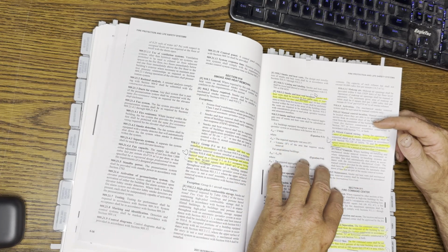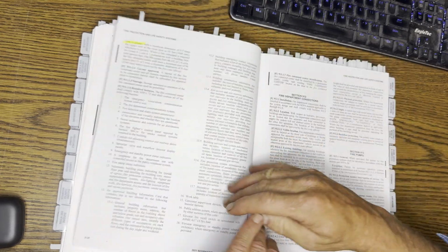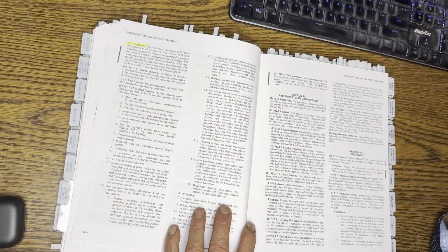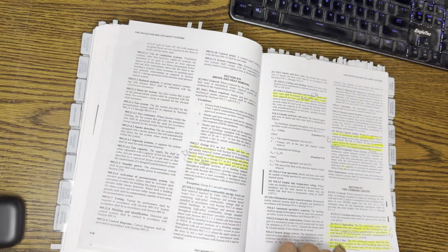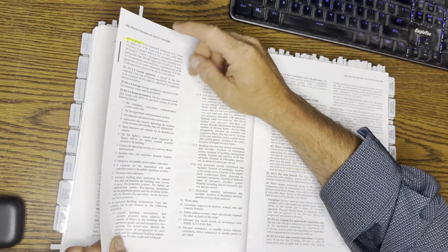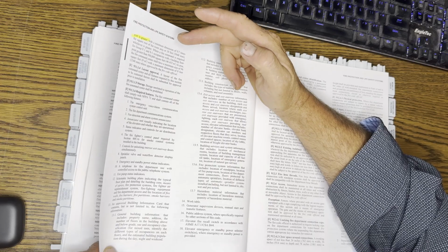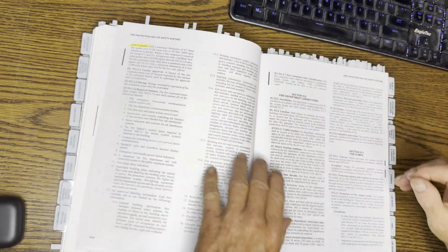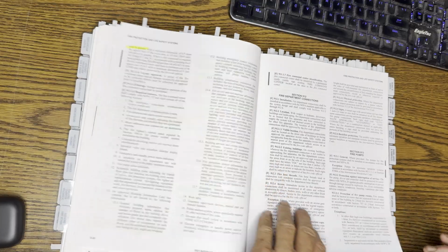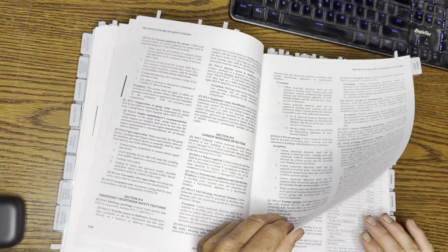Well, where do you go? You go to Section 911. This gives you the parameters. So you have a high-rise building. What's the minimum area of your fire command center? The minimum area is 200 square feet. But they might also ask you what the minimum width is, and they'll give you some different dimensions. There's a formula here you could follow. It seems like I've seen that on one of the tests I took years ago.